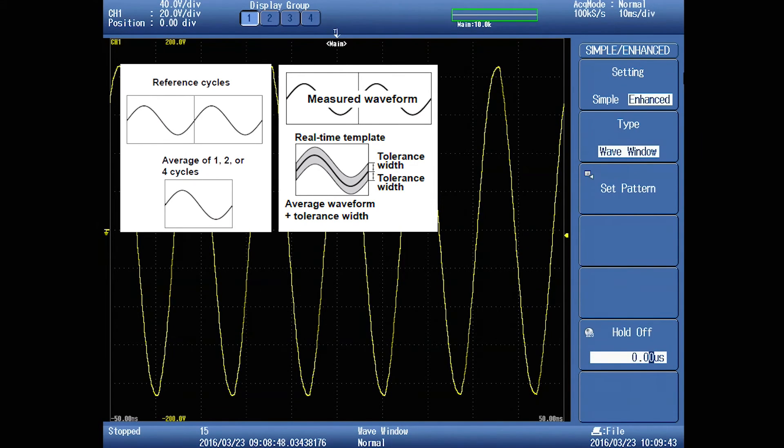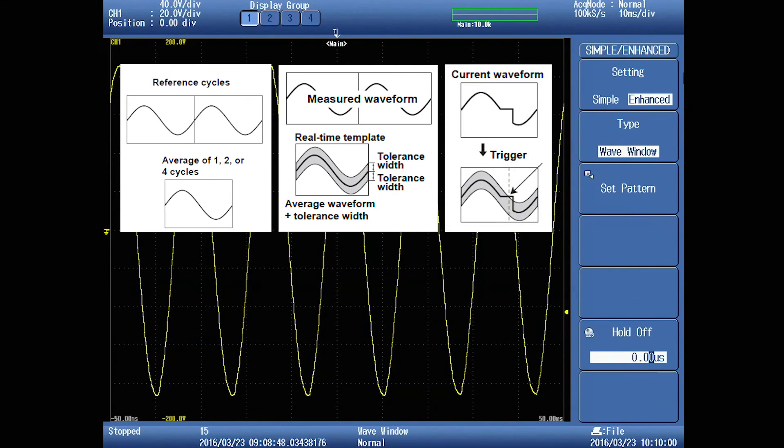As the waveform is being monitored, the scopecorder simply compares each incoming waveform cycle, one or two full cycles of it, up to four, to the previous full cycles of the same waveform. If any anomaly is detected, the scope triggers.